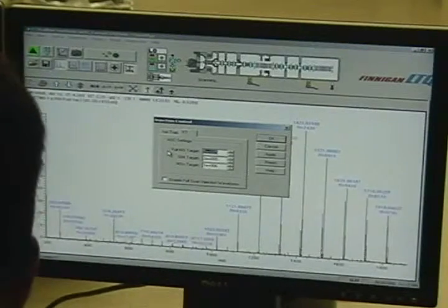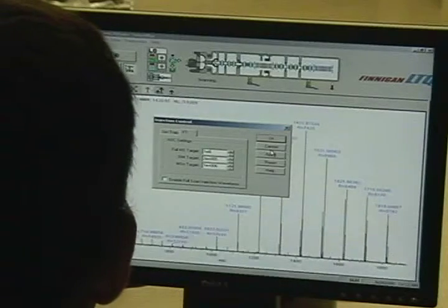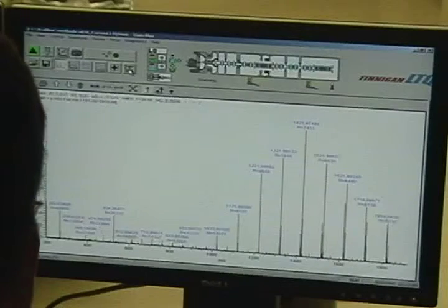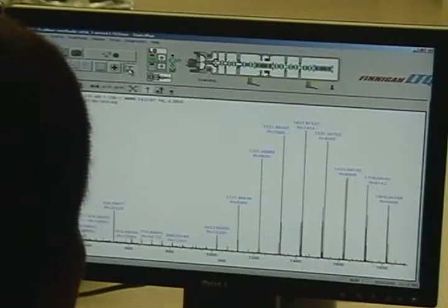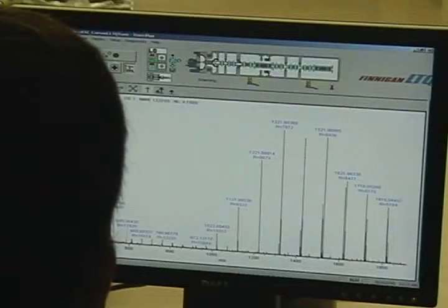Now let's go up to 1E6, where you've been running, which should take my IT time 2x. Right? We double the number of ions. And we're not IT limiting. Right, we're not IT limiting. So don't ever do mass measurements without averaging turned on. We always want to have it on.